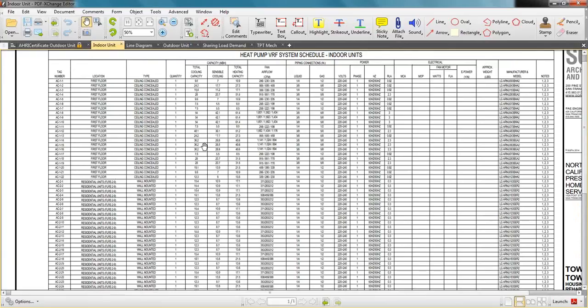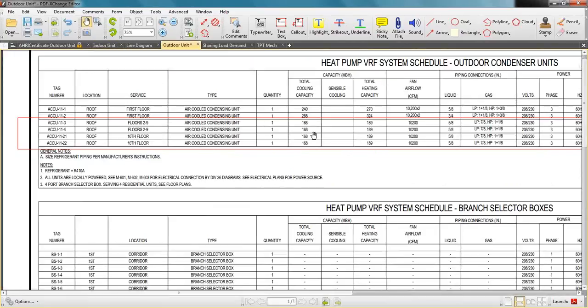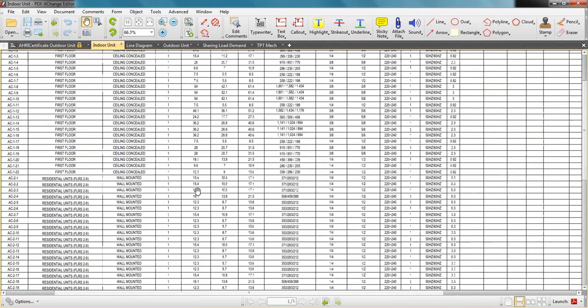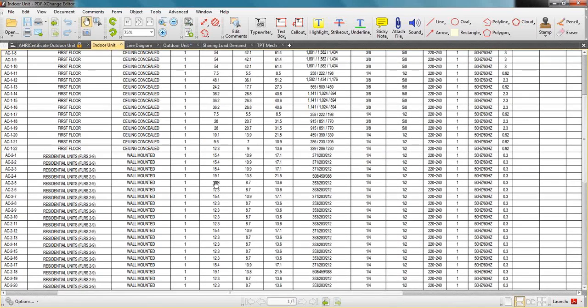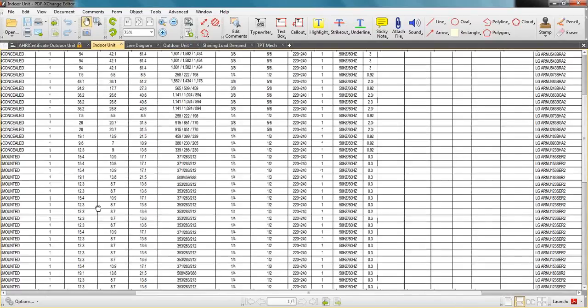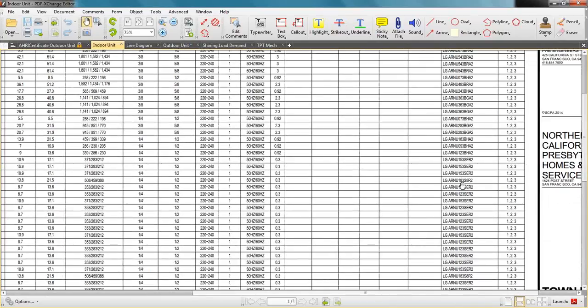So if you remember before, the outdoor unit had 168 MBH. Well, on the indoor units under your MBH, you're looking at 15, 20, 12. So they're sized accordingly, and they're matched up accordingly to what their demand needs. So as you add up those capacities, they should be within that 168 MBH total capacity, and they get to work together and share load and all that good stuff. Over here, it tells you what your indoor unit is going to be, and which ones are going to be matched up with respect to the outdoor units.